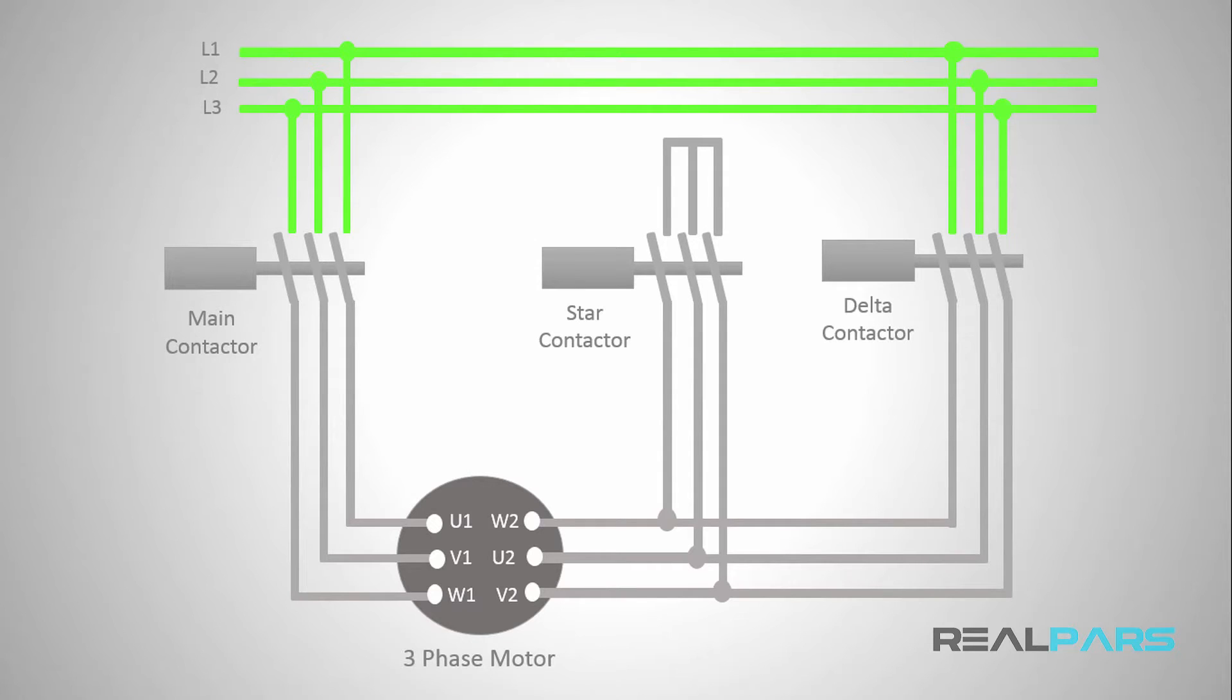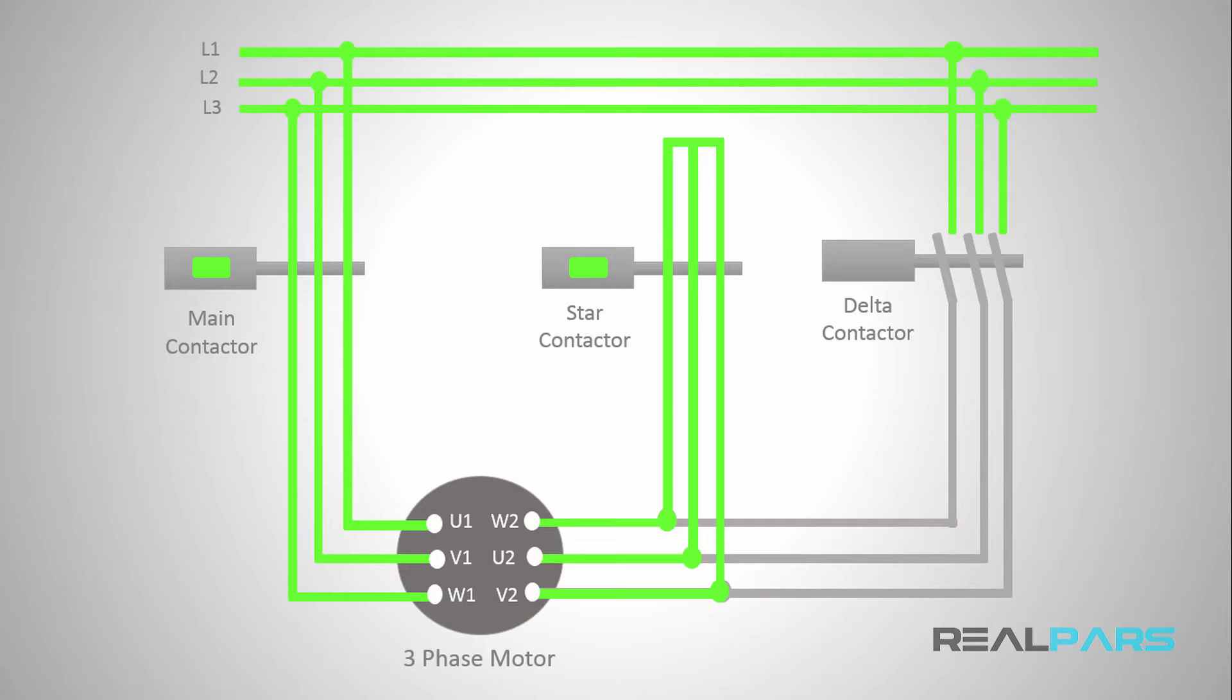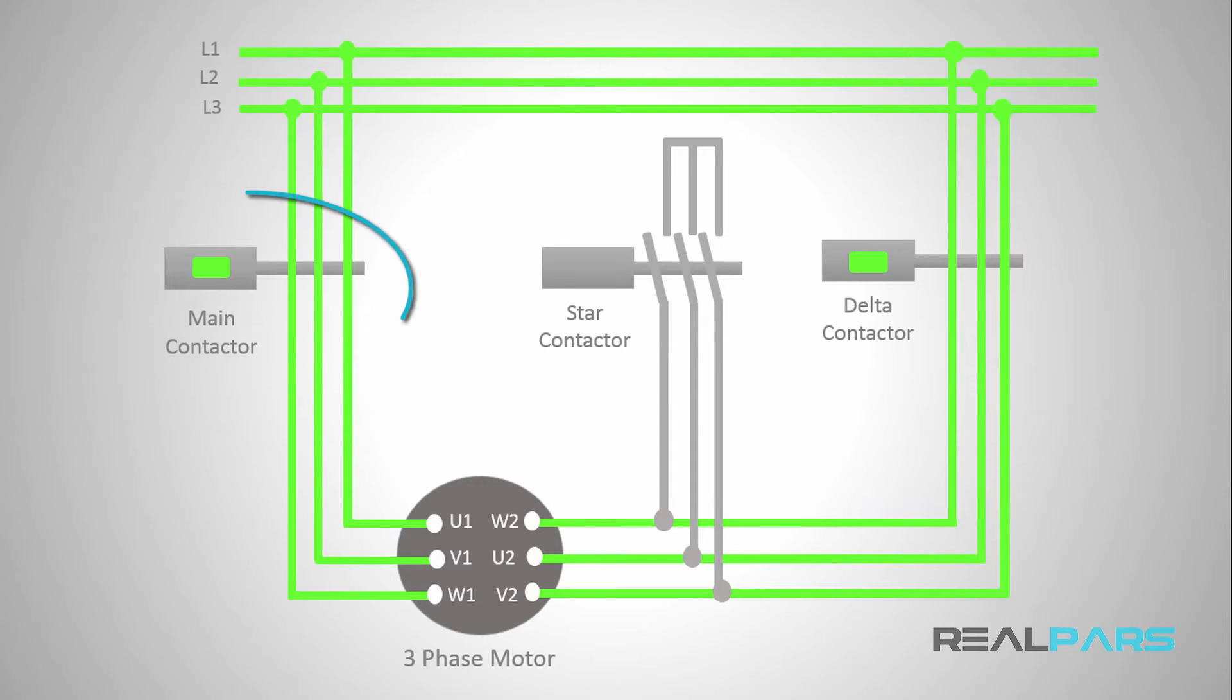To start the motor with the star-delta starter method I need to write a PLC program such that when the start switch is pressed both the main and star contactors will be energized. After a few seconds the star contactor will be de-energized automatically and the delta contactor will be energized all while leaving the main contactor energized.